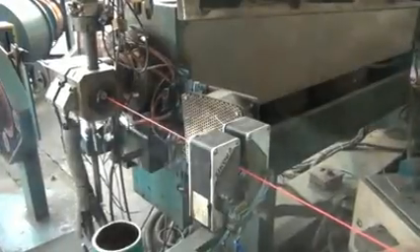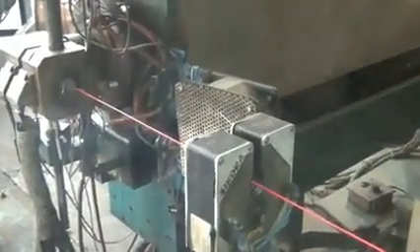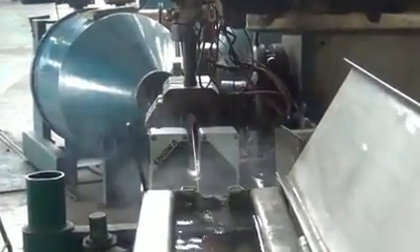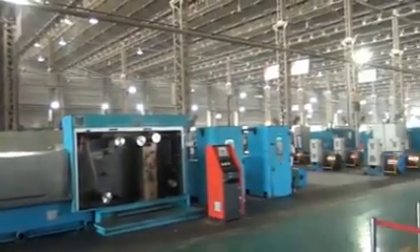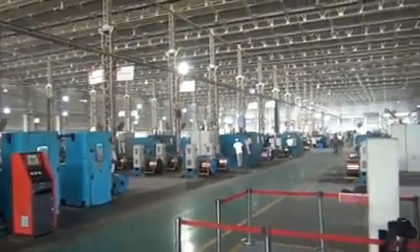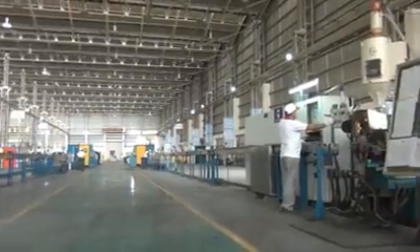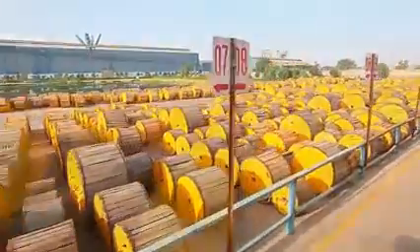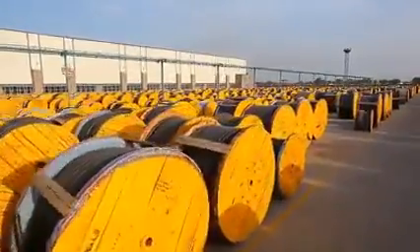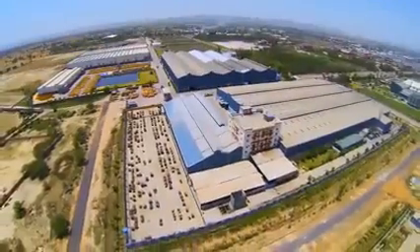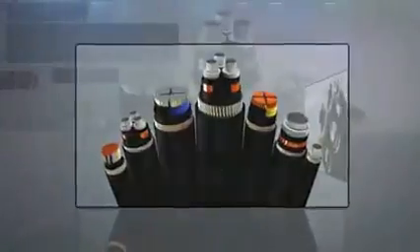The PVC insulation is done in double layer process. First layer with virgin PVC of insulation and outer layer which is very thin and commonly called skin with color PVC. It is done to avoid the adverse effect of color pigment on insulation resistance value of PVC, as the virgin PVC insulation has very good insulation resistance. Havells cables are the first to get the BASEC certification in India amongst many other certifications. Today, Havells cables have become synonymous with superior quality and safety.